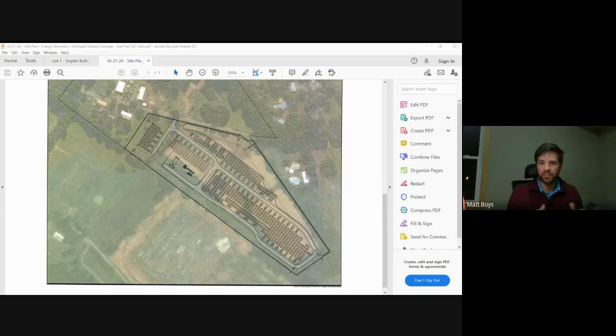If for any reason the facility loses connection with our 24/7 monitoring—of which we have at least 2 ways to connect to the facility remotely—the facility goes into automatic safe mode, where it just shuts down. It doesn't discharge energy, it won't charge the batteries. That's its default safe mode for any reason, even if it's just a connectivity issue with our monitoring system.